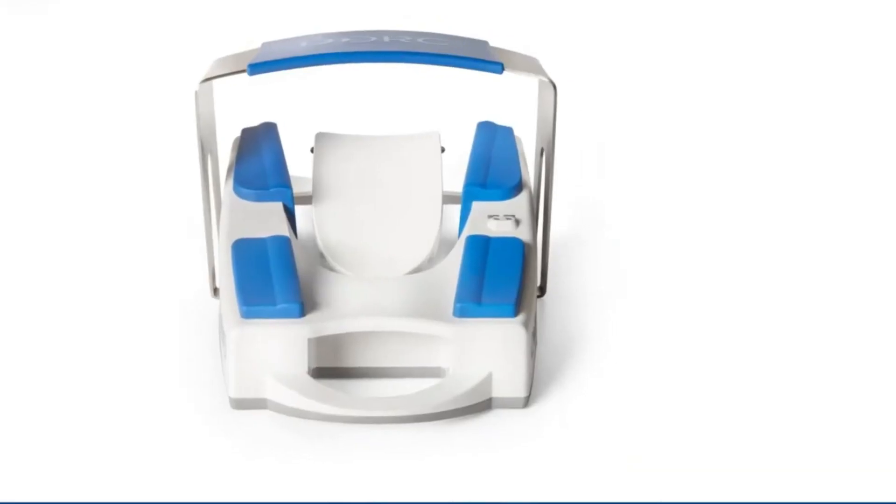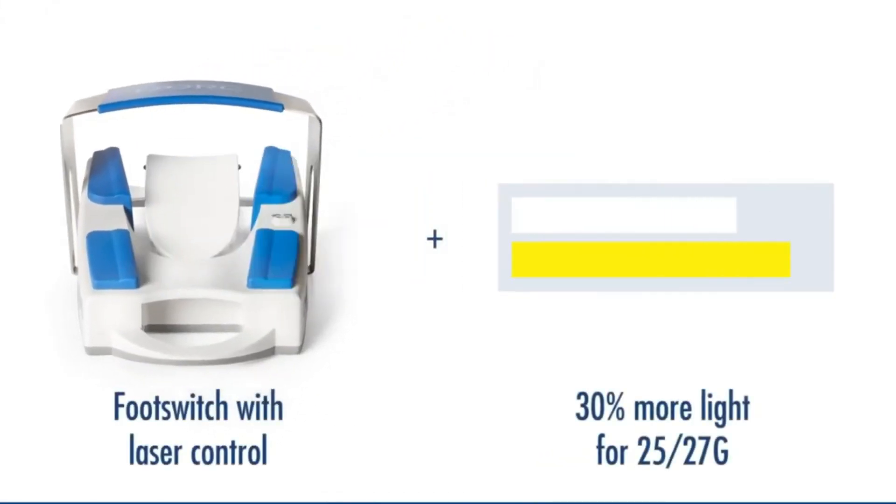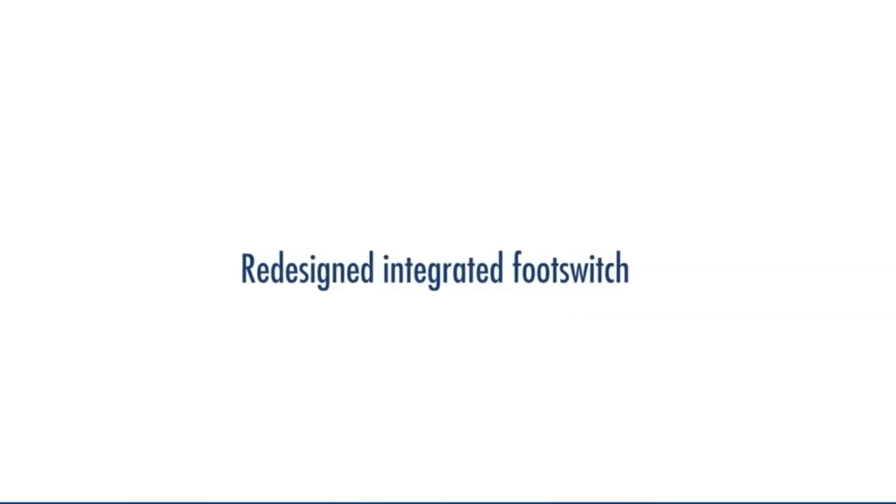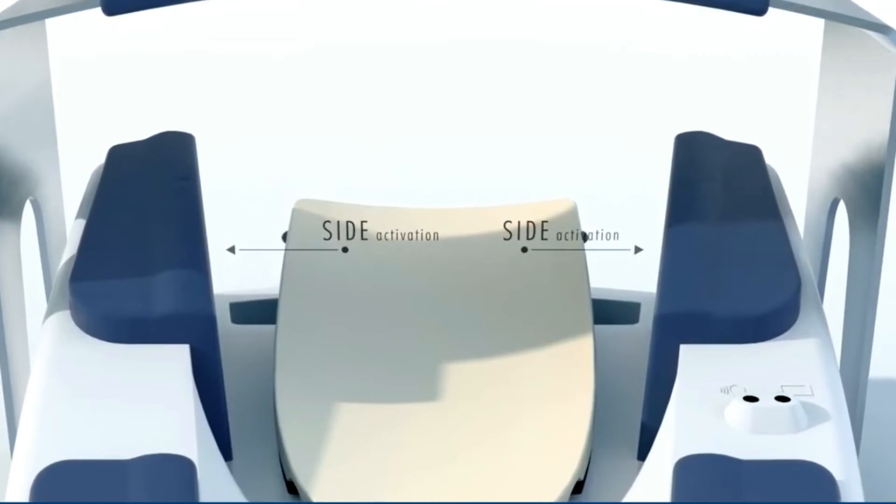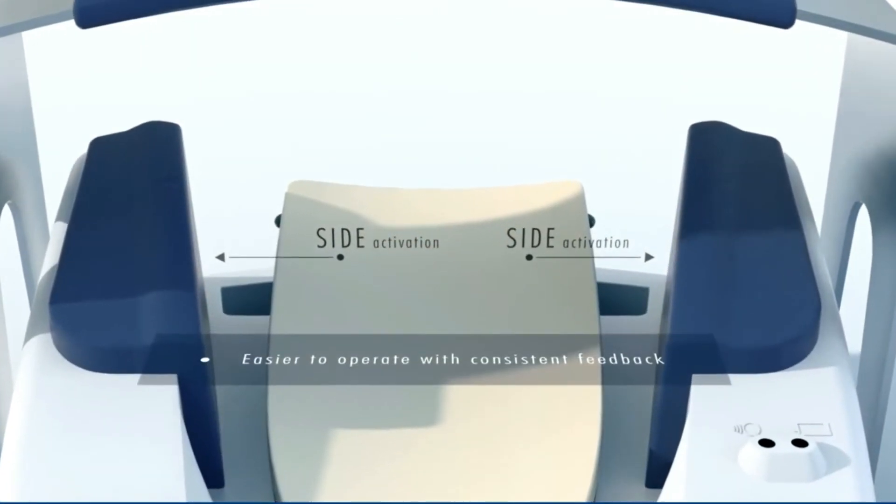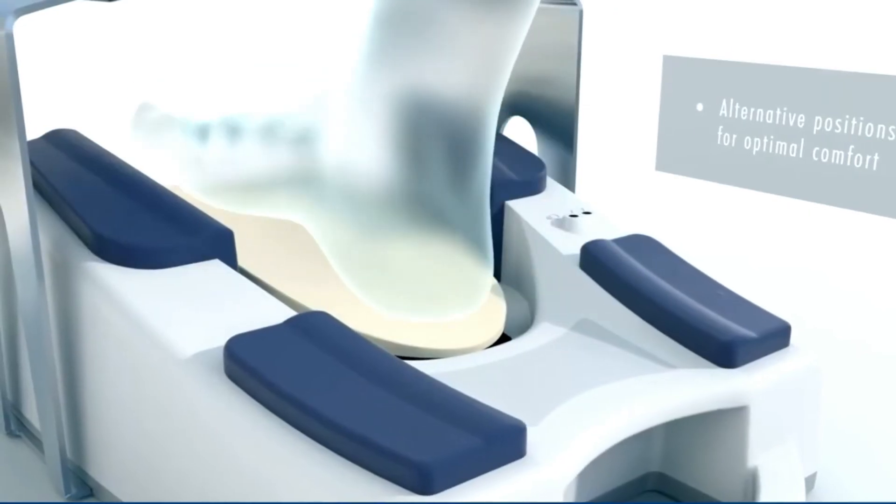The fifth component is the foot switch. Phaco emulsification is a form of cataract surgery that uses a foot switch to control the irrigation, aspiration, and ultrasonic power delivery to a probe that breaks up and removes the cataract from your eye.